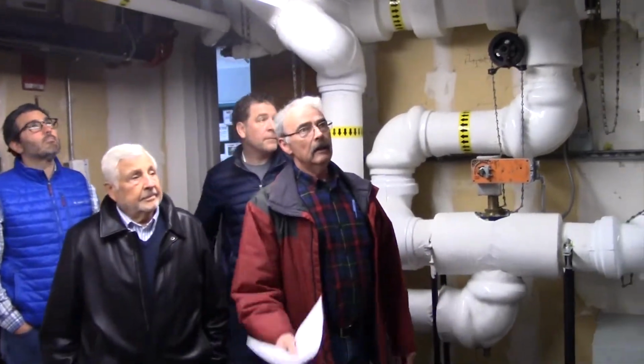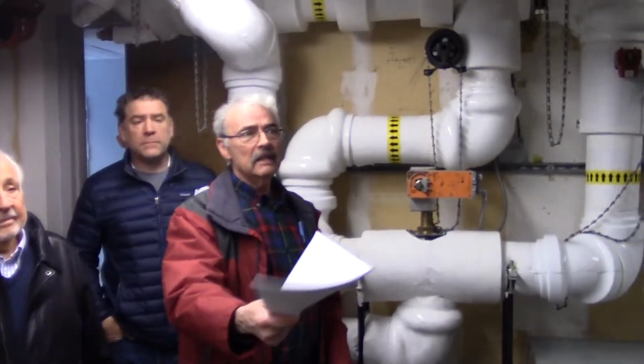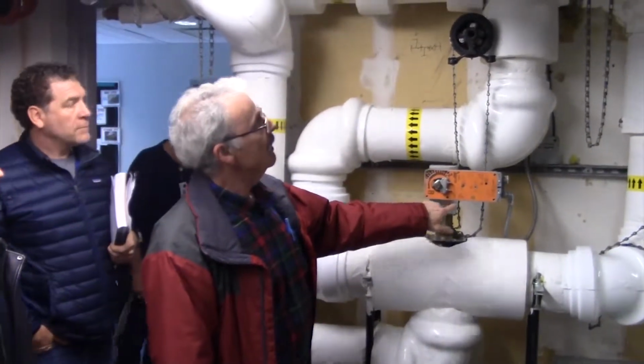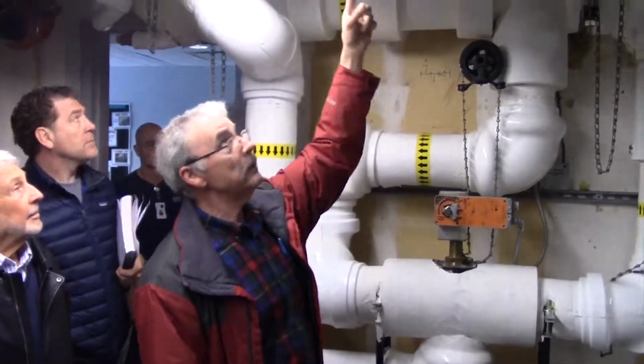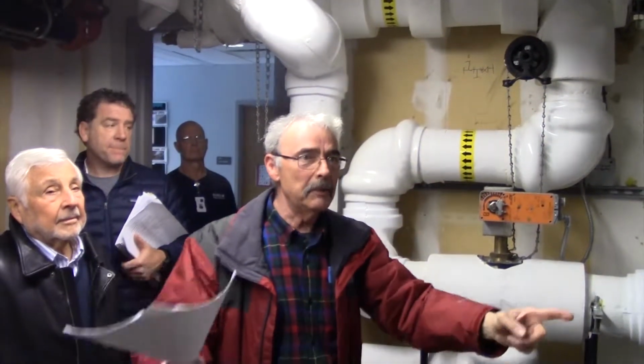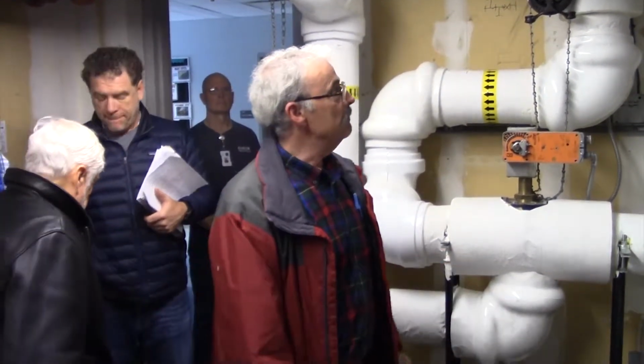Separate, and we've involved moving some mixing valves, etc. We moved it over to here, right here now. Redid the piping coming up here, coming over this way. Redid the piping over the boilers themselves. Put two additional pumps. They're little black units up on there. They've each got mini computer processors on them to regulate the flow. It's tied into our computer system, and it's a more efficient way of heating.